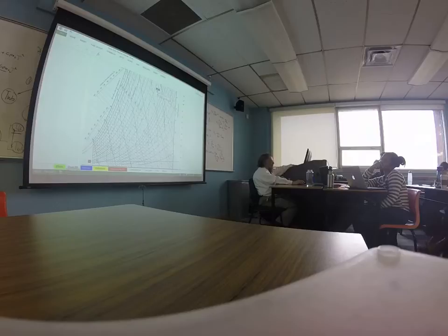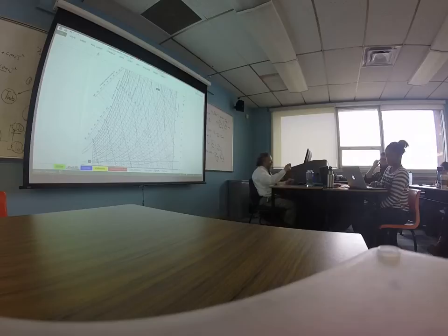So we should be having these kinds of readings in our wet and dry bulb thermometer at the end. This should be the reading that we get in the dry bulb at the exit of the bottom of the spray dryer. So what we can do is tweak some of the things so that our little model more or less follows the experimental data that we have.